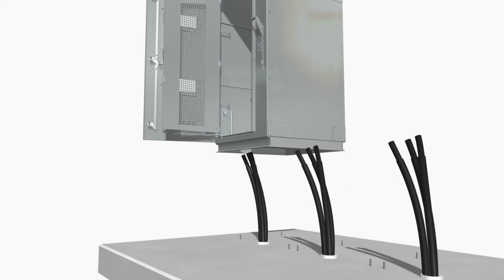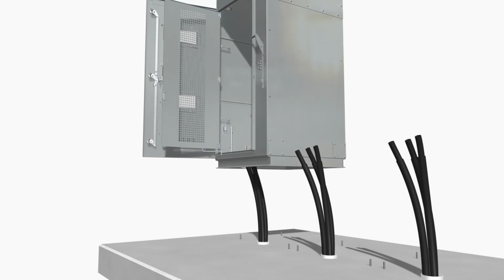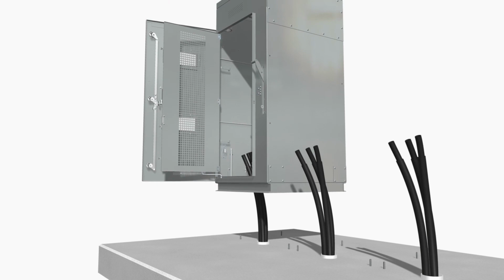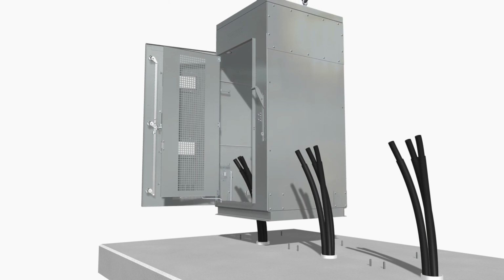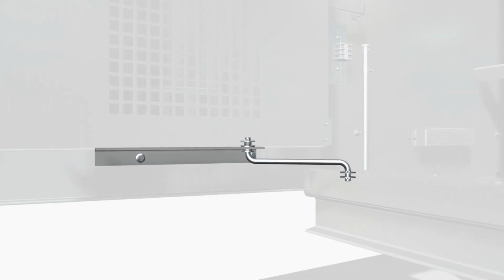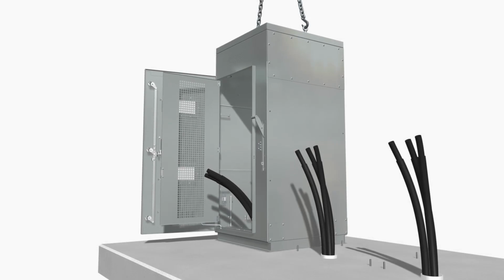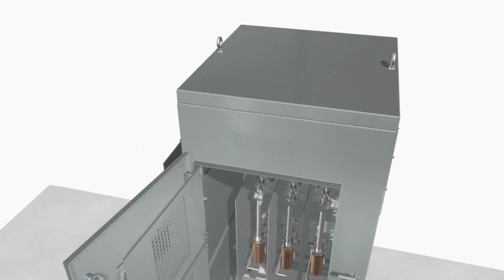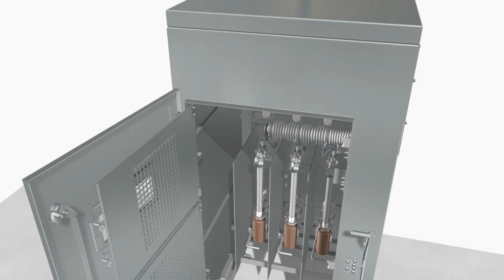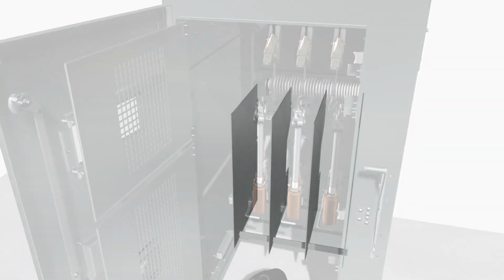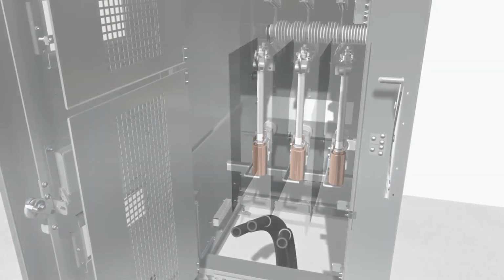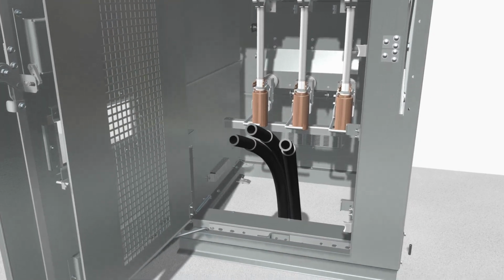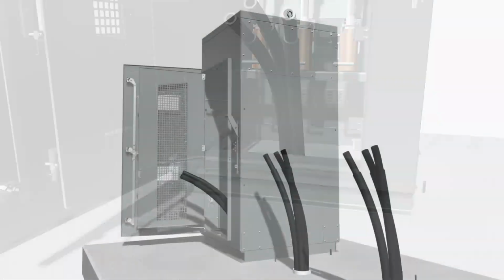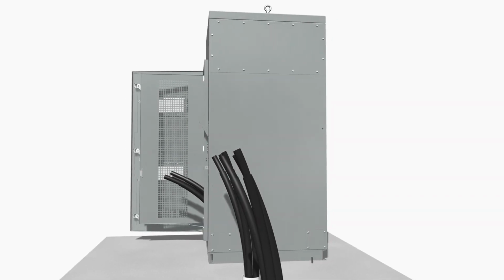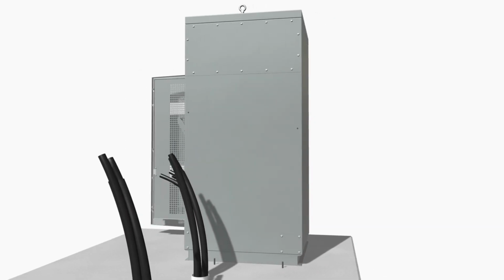If excess lengths of direct buried cable are in place and it is desired to feed them into the bay as the unit is being lowered, the doors must be opened with door holders latched to allow any excess cable to be fed over the door stiles. If the interphase insulating barriers are removed to facilitate this procedure, note their positioning to ensure correct reinstallation. It should not be necessary to remove any end barriers.